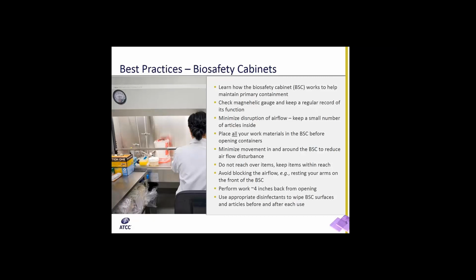Avoid blocking the airflow. For example, resting your arms on the front of the BSC will actually prevent the smooth flow of air in the grill that is immediately in front of you. Do not overreach for items, and keep all of them within reach so you are not disrupting the airflow within the cabinet.